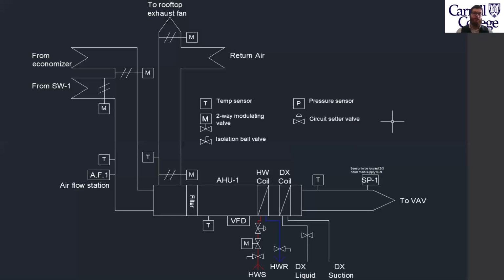This detail shows how the solar wall is connected to the air handling unit. The solar wall is connected in parallel with economizer cooling air. Economizer air is just plain outside air at outside air temperatures. This is mixed with the solar wall air so that a constant temperature can be provided to the air handling unit. If just solar wall air was used, it would be too hot. The air is then also mixed with return air from the building to provide a constant temperature for the air handling unit. This is set at 50 degrees and then is heated with the hot water coil in the air handling unit to 55 degrees for output.